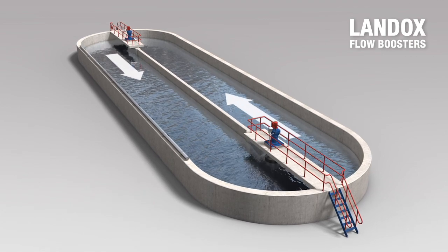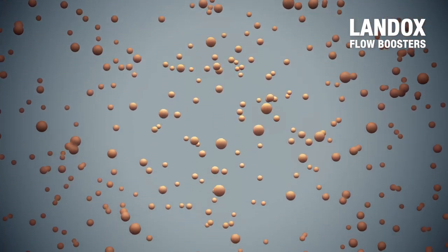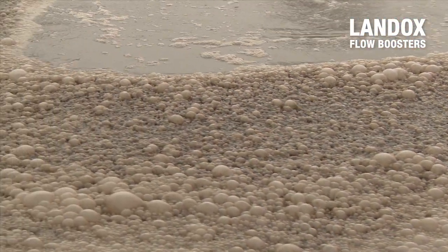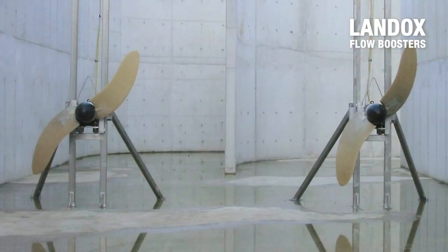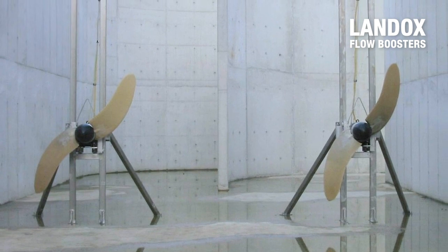An even bigger saving is realized by fine bubble aeration. Small bubbles perfectly reach the surface, and as these bubbles remain small, a maximum surface is created for optimum oxygen transfer into the water. A conventional propeller creates a turbulent flow, and small bubbles will then coalesce into large ones, automatically transferring less oxygen. This means the fine bubble aeration system has to operate more often.